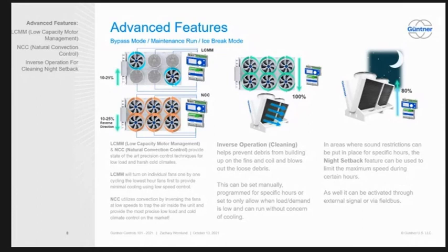Our previous controller, the GMM EC, that's our legacy controller. That one, you needed an inverter if you wanted 10 to 0. An ARM board. With our newest controller, it's baked in, so it's just a setting on the controller. That's another call I get sometimes, where it's been set up but the signal's not inverted. That's an easy fix. It's just going into the settings and inverting the signal.